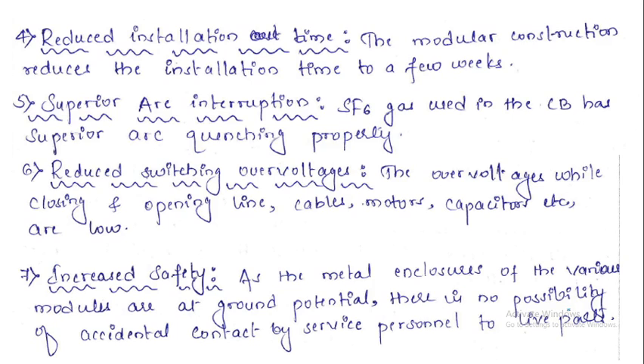Superior arc extinction or arc interruption. As we already learned, SF6 gas has a greater dielectric strength compared to air. So the arc interruption or arc quenching property is very much superior compared to normal air insulated substations. Reduced switching overvoltages. The overvoltages while closing and opening lines, cables, motors, capacitors, etc. are low compared to a normal conventional air insulated substation. So the switching voltages will be very low.